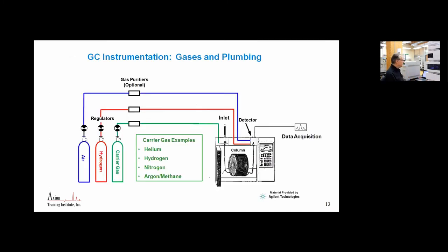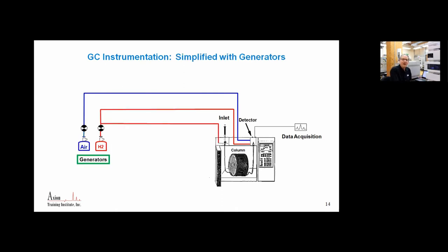Just another pretty plot I'd toss in there for you. This shows the different column diameters. It explains why we like small column diameters. Smaller diameter column, thinner films, give us that flatter Van Deemter, that ability to go fast and not lose the quality of the analyses. So a couple of practical things here. This is the typical GC instrumentation plumbing. Usually we have three tanks sitting in the lab. We have helium as our carrier gas, hydrogen and air for our FID detectors. Now we have some options here and one of the options is to use hydrogen for both hydrogen fuel for the FID and for carrier gas.